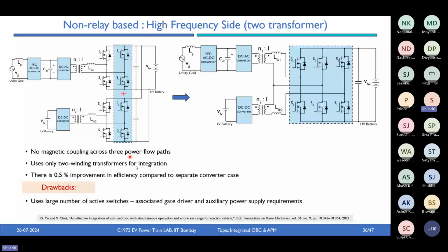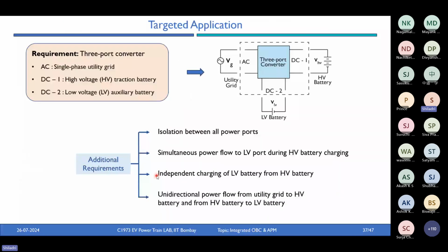Now I'll talk for the next 5 minutes or so about a specific targeted application we looked at: charging a high voltage battery and a low voltage battery. Along with the basic requirements of isolation, simultaneous power flow, and independent charging, we were looking at an application where we were okay with unidirectional power flow from the utility grid to the HV battery, and from the HV battery to the LV battery. This is the use case for a large number of cases in industry and commercial products right now. People talk about V2G and V2X as future features, but these are things you will not immediately find in most chargers, even for four-wheelers.